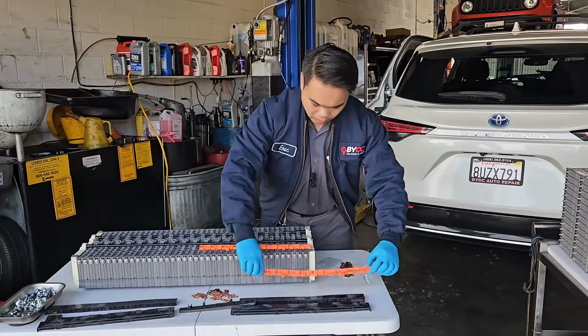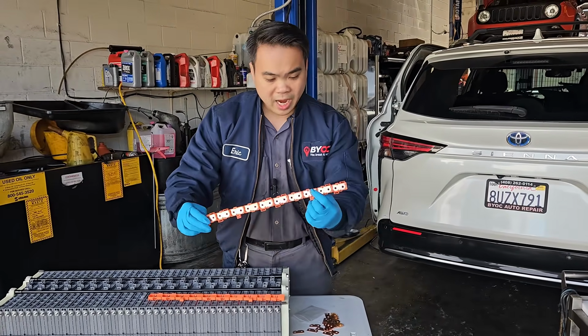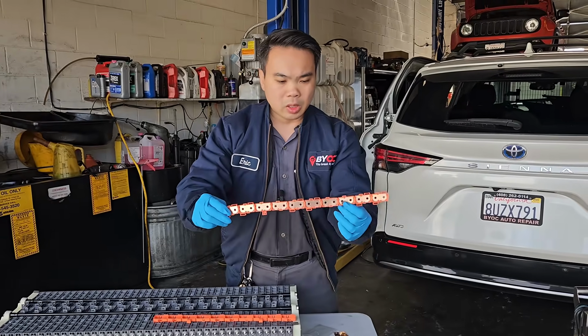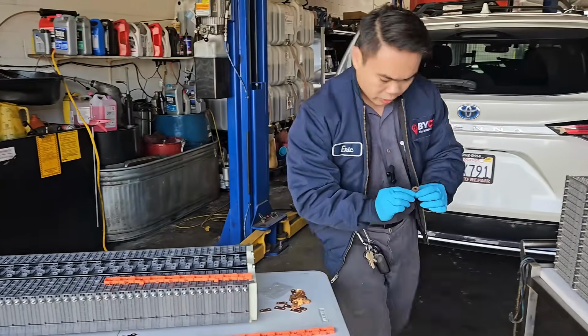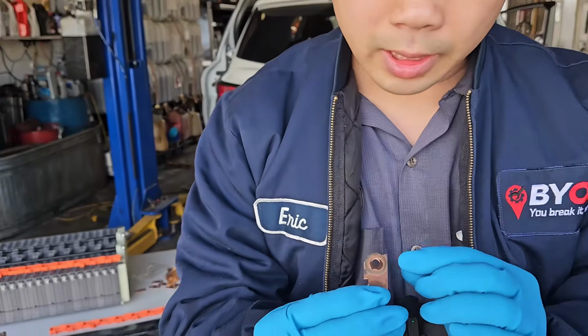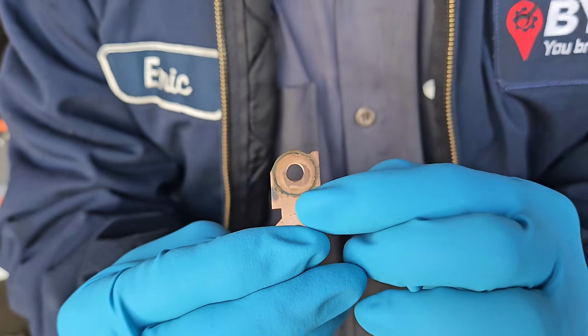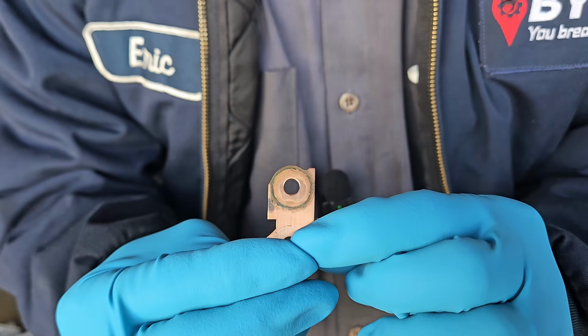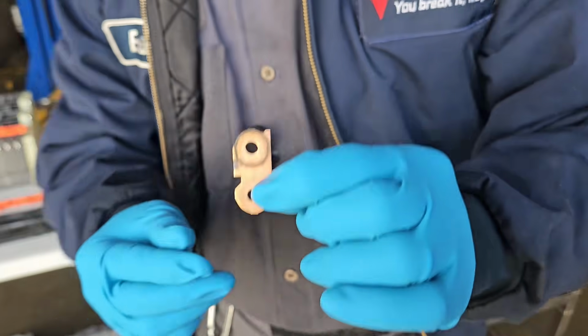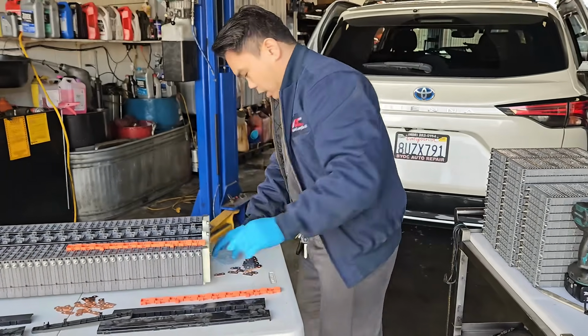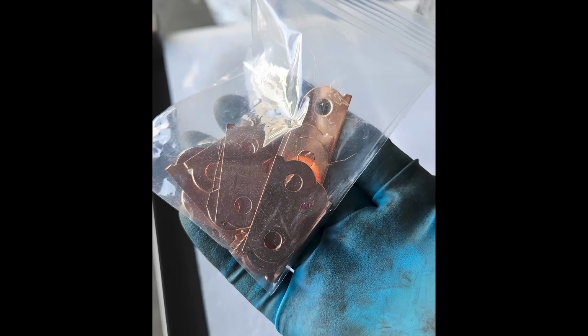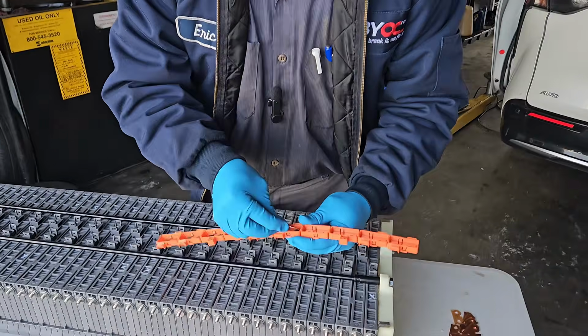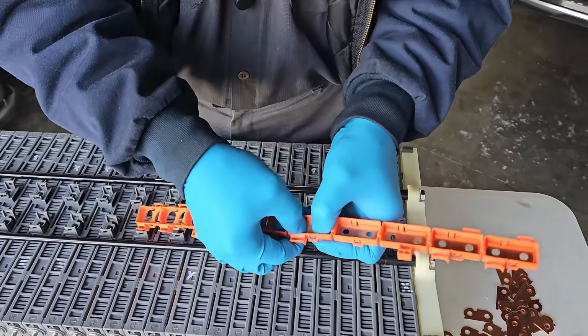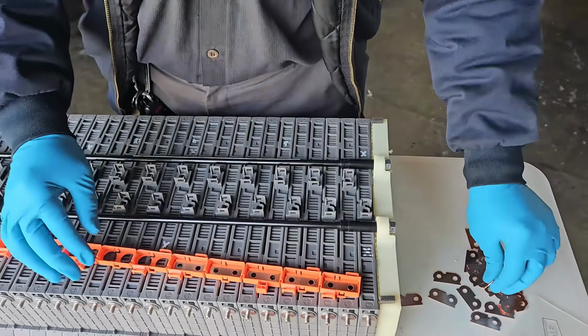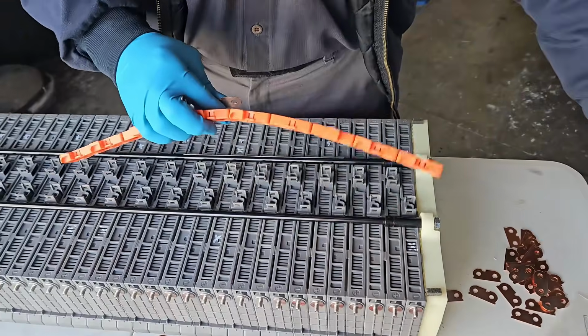So here's our bus bar, and we have to make sure we replace all the plates over here. They do get corroded over time, you can see the corrosion building around the plate, and they need to be replaced. These come in a baggie in every box of battery. All you gotta do is put it in the right position and snap it right in, and do that for every single bus bar along with the harness over there.